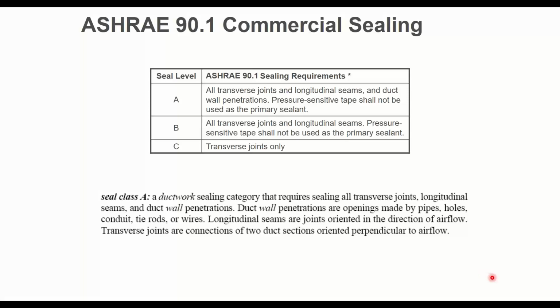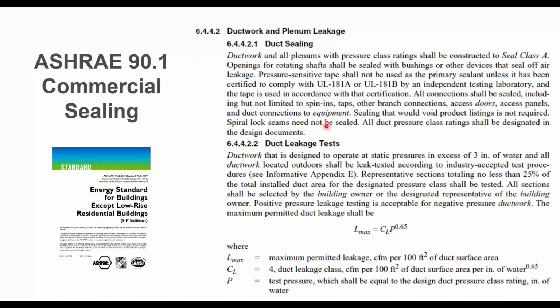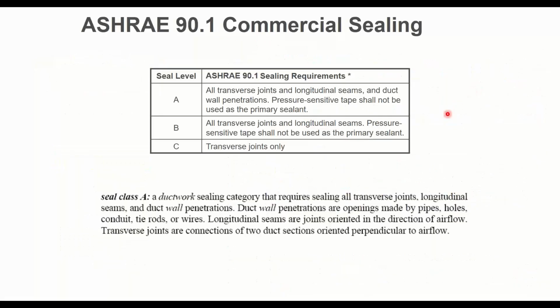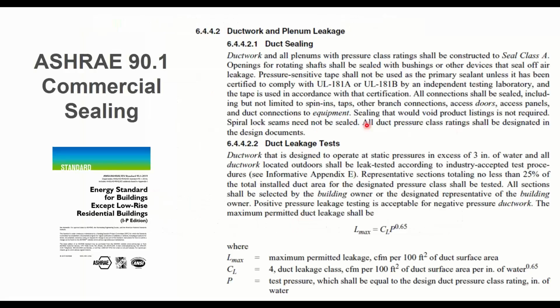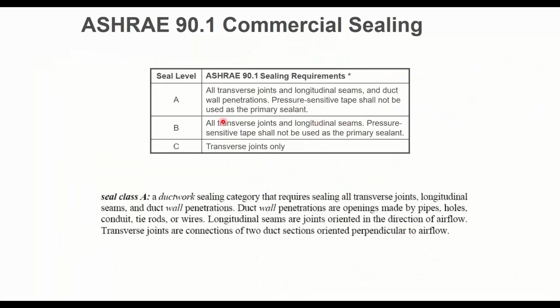And then if you look at the, I should do this in reverse, but if you look at the ASHRAE standards, which is what the mechanical codes and energy codes feed off of, everything has to be seal class A. It used to not be that way. Sometimes it would say you do B or C. Now it's all A. So basically, they don't even need the language anymore. Get rid of the language. Do everything in A. So seal everything. Every kind of duct system, seal it, seal it, seal it, seal it up. There's no exceptions. Oh, it's only return duct.